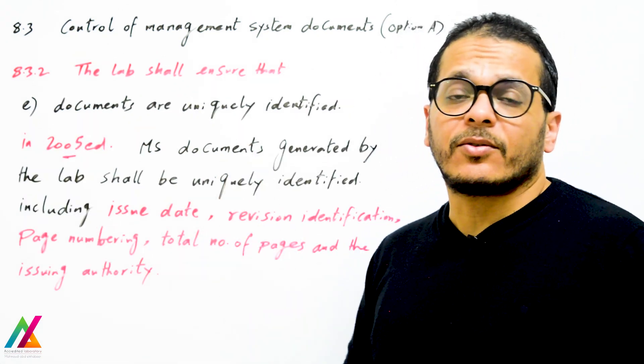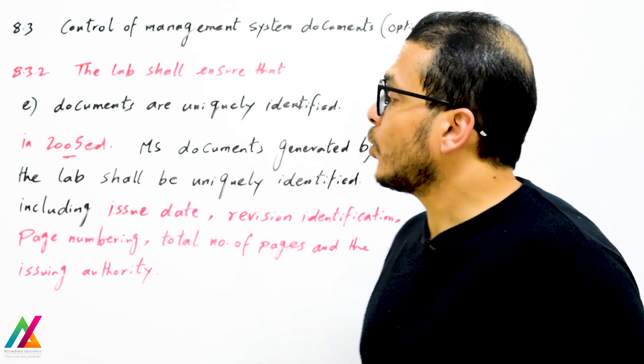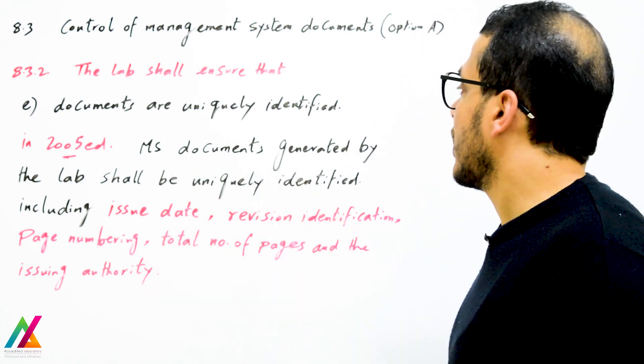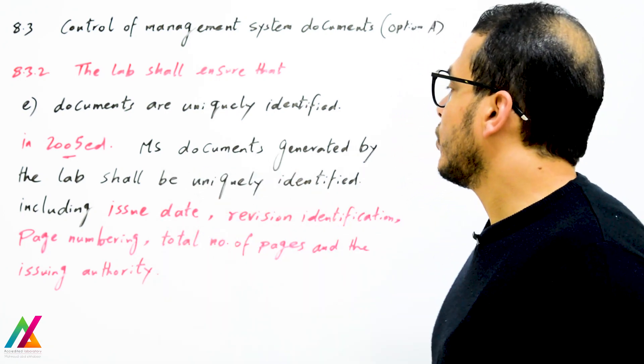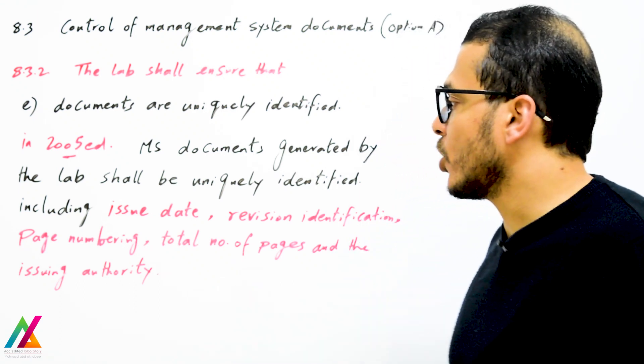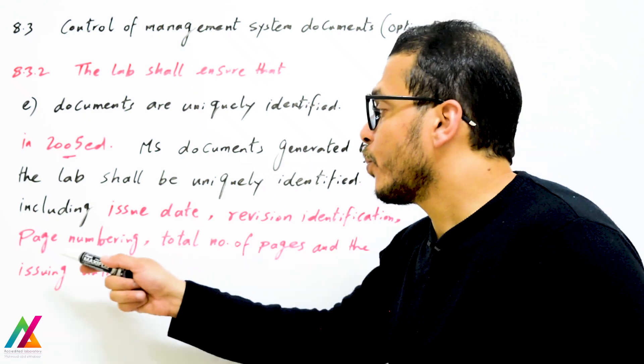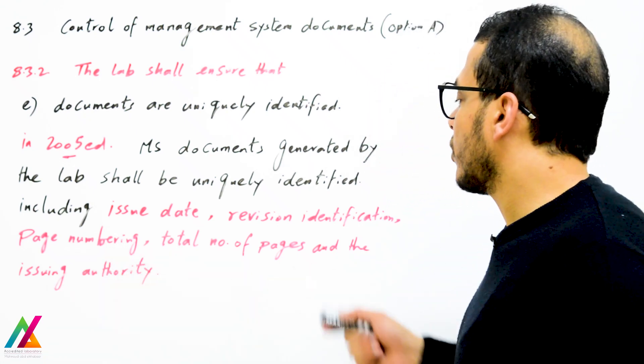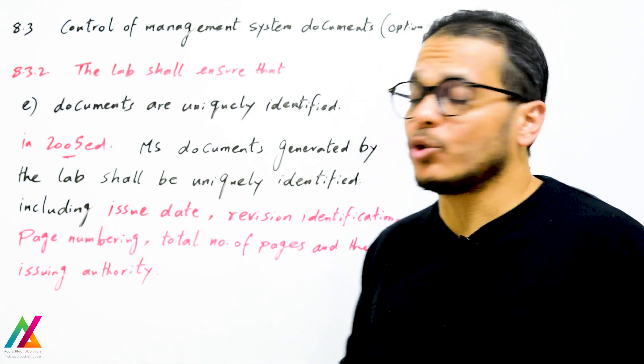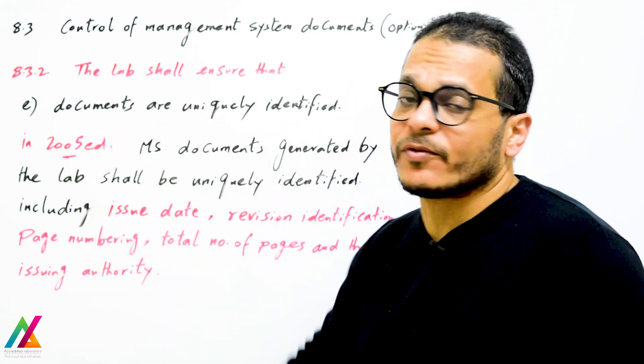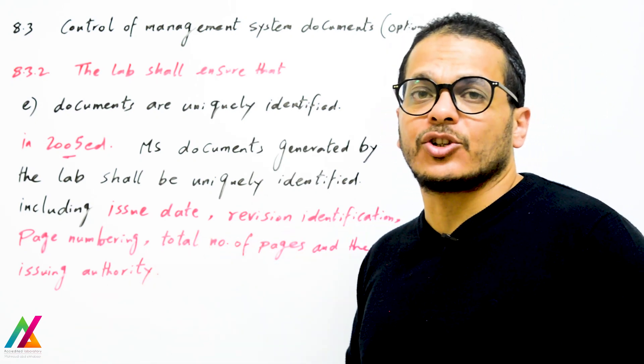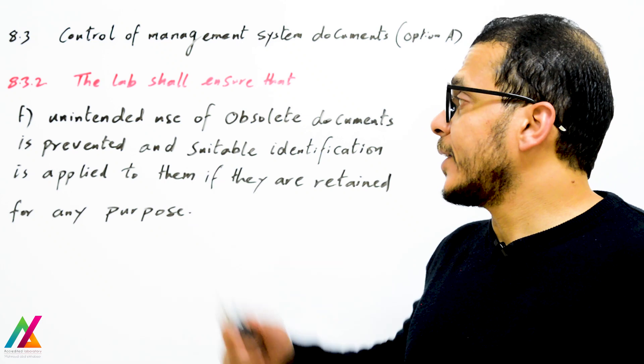The lab shall ensure that documents are uniquely identified. This is more flexible than the 2005 edition, where management system documents were required to include: issue date, revision identification, page number, total number of pages, and issuing authority. In 2017, identification is still required but the specific fields are not mandated — more flexibility is given to the lab.